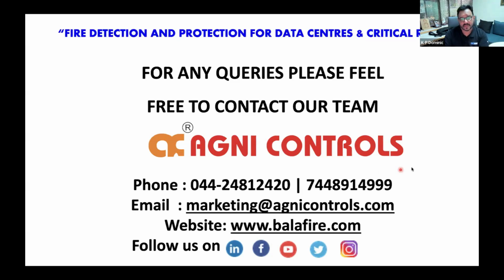It is very dangerous. Not only oxygen, your cylinder can sometimes fly because of pressure, and a pipe can burst. So it is always advisable, whether it is poisonous or toxic, to evacuate when there is a discharge. Is a special certificate necessary for dealers and vendors of fire extinguishers? What Mr. Arun Kumar said, if it is 20 bar and above, you need to get a special certificate.